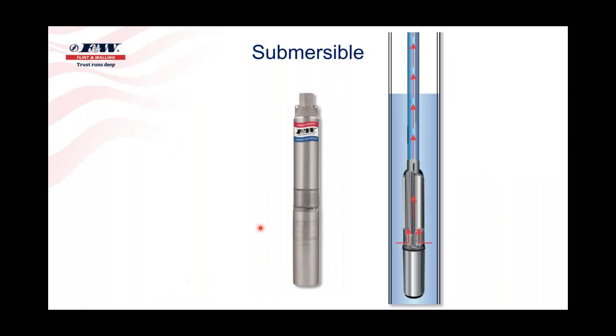A submersible pump, unlike an above ground pump, utilizes what we call a water cooled motor, where all the above ground pumps are air cooled. And when a pump is put in a well, like you see here on your screen, that cooling is almost natural in effect. So as this pump is running, we get water moving past that motor into this screen and on out the discharge up to the top. And so you get a natural flow of water moving past that motor, which helps dissipate heat and carry that heat away.